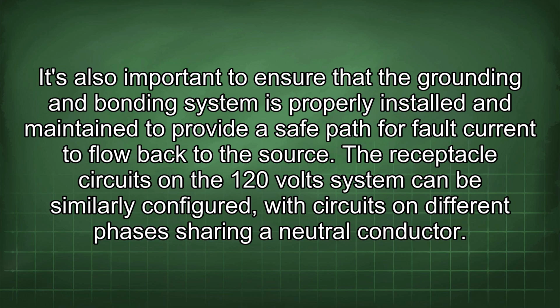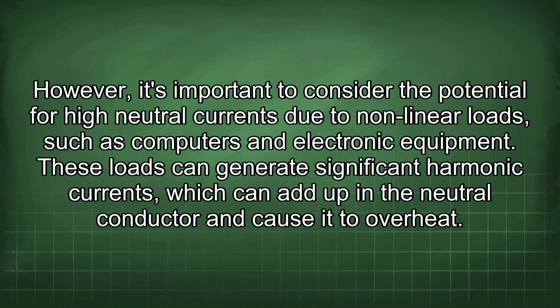The receptacle circuits on the 120-volt system can be similarly configured, with circuits on different phases sharing a neutral conductor. However, it's important to consider the potential for high neutral currents due to nonlinear loads, such as computers and electronic equipment.